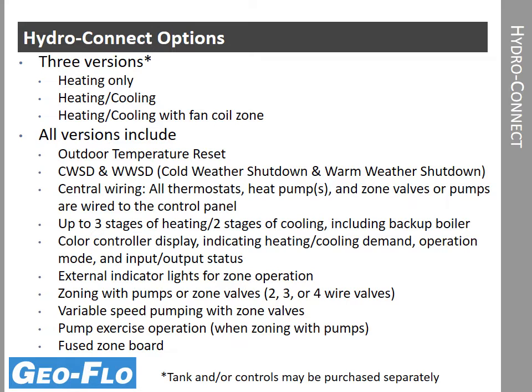The controls can be purchased separately from the tank or with the tank. Regardless of which control version you go with, all versions include outdoor temperature reset, cold weather shutdown, and warm weather shutdown, which stops conditioning the tank when the temperature is mild. That's an energy saving feature. Otherwise, the tank is going to be conditioned as chilled water or hot water.